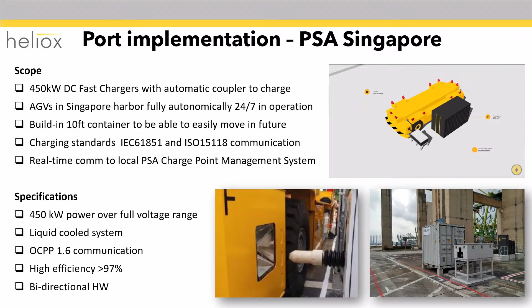Specifications of the charger: 450 kilowatts, liquid-cooled, so the internals of the container are fully isolated from the external environment. Communication goes via the Open Charge Point Protocol, allowing us to feed information back not only to the PSA port authority, but also to the Heliox back office, ChargeSight.